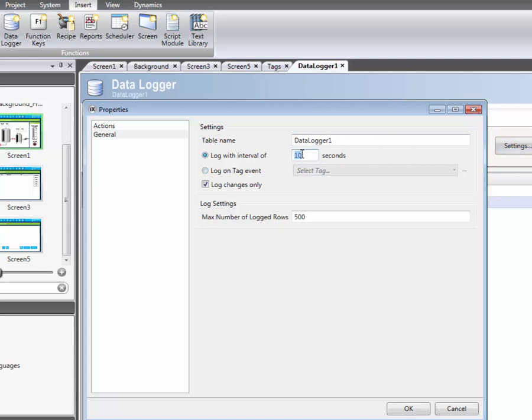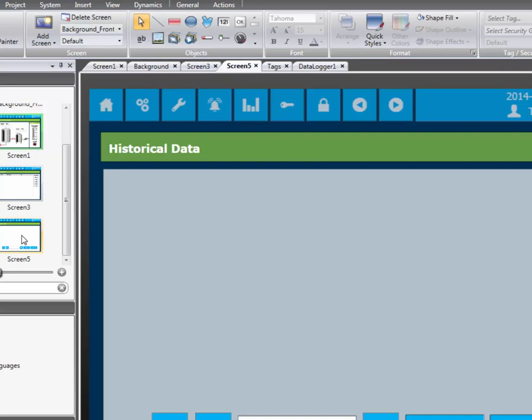The max number of logged rows is changed to 3600, which means that we will have a rolling one hour history. The data logger is now configured and will collect data when the application is running.